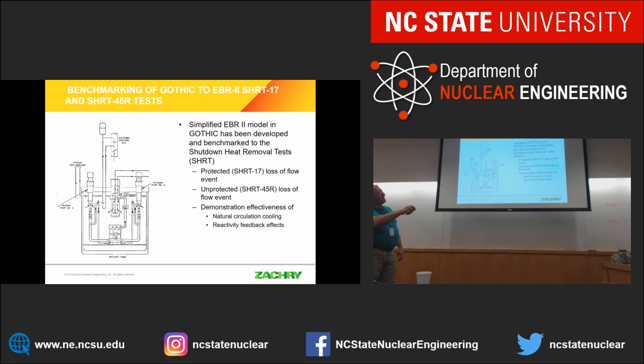For the shutdown heat removal tests, they ran two tests. Well, they ran more than two, but these are the two of which they have data that's available for benchmarking. SHRT-17 is a loss of flow event. Protected, meaning the reactor was scrammed, and an unprotected event with a loss of flow, meaning the reactor remained online, okay? And effectively, it shut itself down because of reactivity. The intent was to demonstrate the effectiveness of natural circulation and reactivity feedback effects, okay?